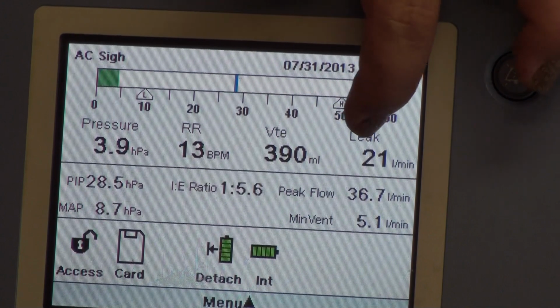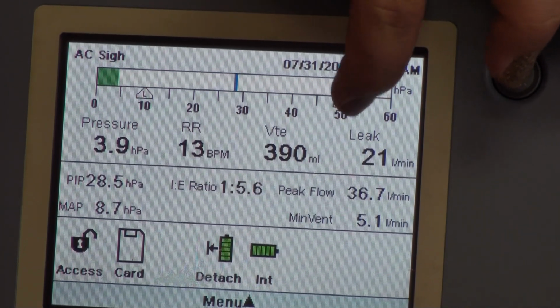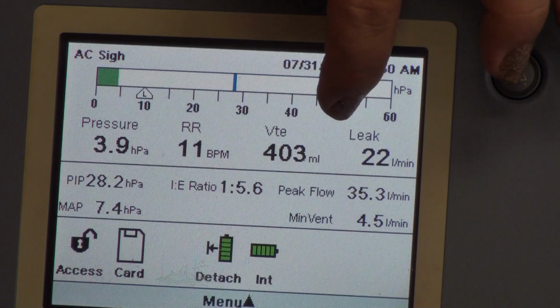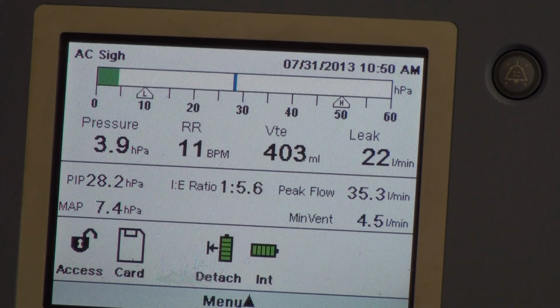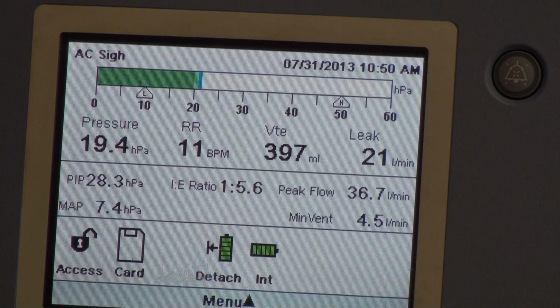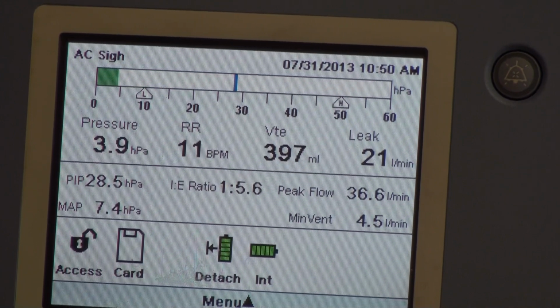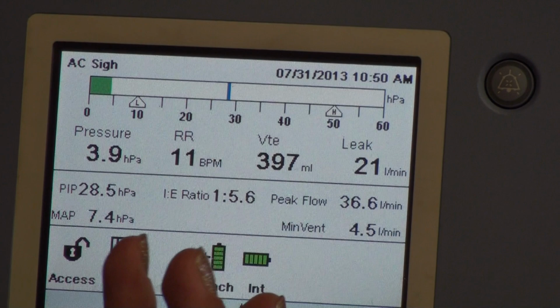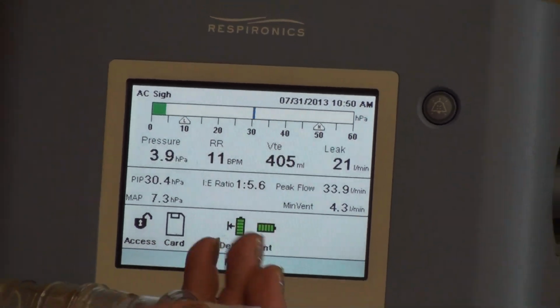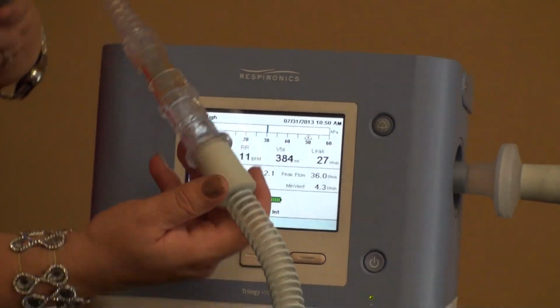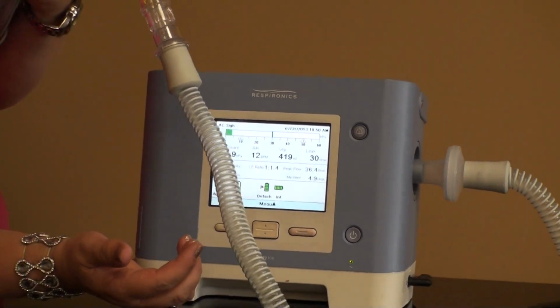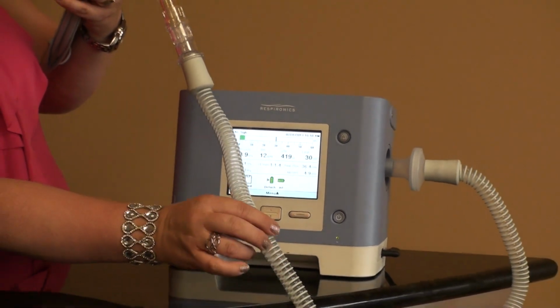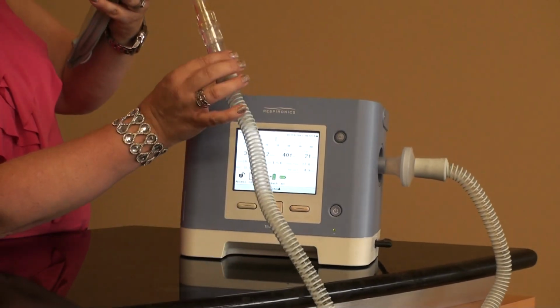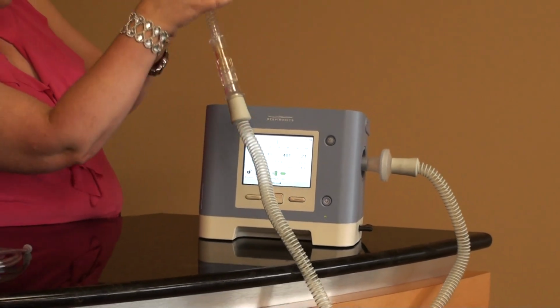And then L is going to be my displayed leak. This here is going to be my total leak. Now, this is kind of confusing to some people. Respironics, if you've dealt with Respironics brand stuff, has the technology in it that allows for leaks in the circuit that it can compensate for. For example, because I have a passive circuit on here, I have constant flow coming out of this around here, my exhalation valve, okay? Constant flow. So to ensure that I have 500 or 400 coming into my client, I maybe deliver 420.